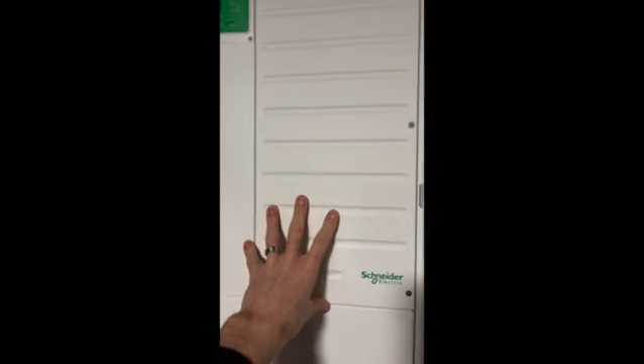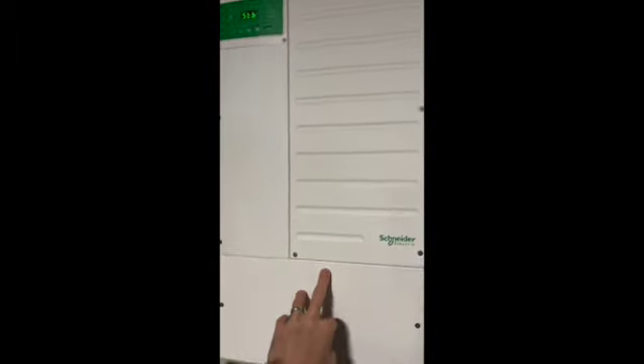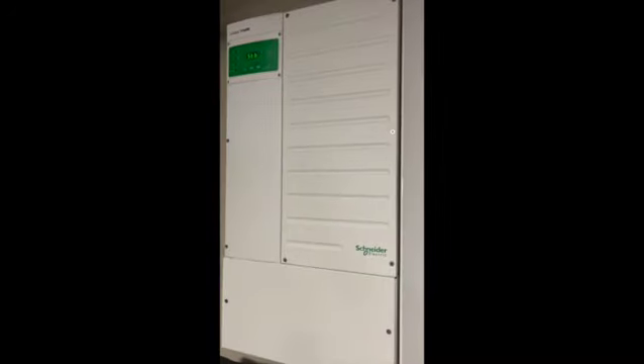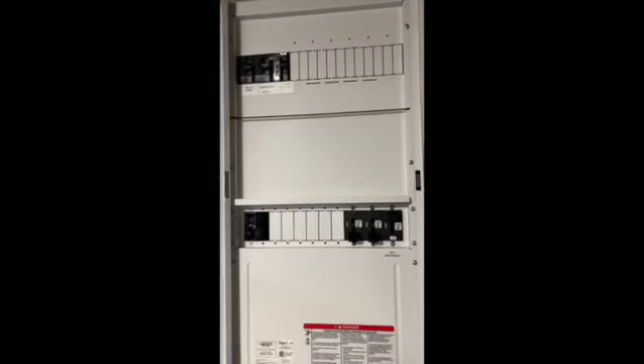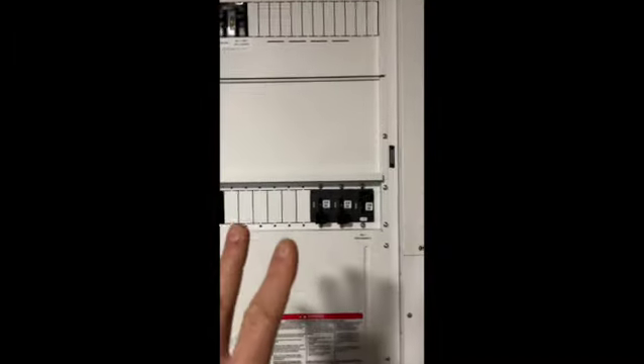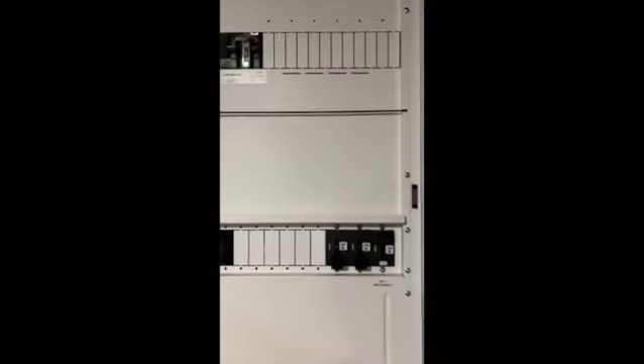Our usage is high — we use 2,000 to 2,500 watts an hour. I'm running the full Schneider setup: two XW Pros running my off-grid, and one XW Pro feeding back to the grid, which will also be my backup. So then I can pull power from them if for whatever reason my off-grid isn't keeping up, like if the sun is low, to pump up my batteries. These things are amazing. Nothing's wired up yet on this system.